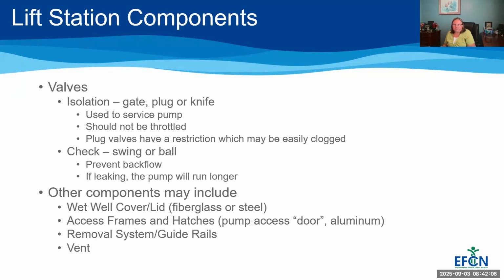We typically see gate valves here. Plug valves have a restriction that can be clogged more easily, but sometimes there are plug valves or knife valves used for isolation. And then check valves. Of course, we have check valves, and they're swing or ball check valves. It prevents backflow, so the pump turns on and water's in that pipe, and then when it turns off, you have a check valve so the water's not flowing back into your pump station from where you were trying to get it to go to. If your check valves are leaking, then your pumps have to work longer. They have to work harder. So you want your check valves to be operational and to work the way they're intended.